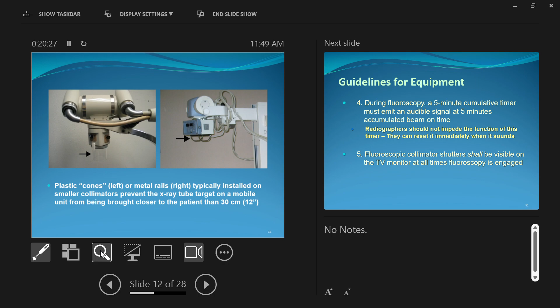In fluoroscopy, which is video x-ray, don't worry too much about this, because you don't do fluoroscopy, right? There has to be a 5-minute cumulative timer. Every time we turn fluoroscopy on, it adds time to the timer. Once 5 minutes hits, we have to have an audible signal that lets everyone in the room know we've hit 5 minutes of fluoroscopy time. It is then the radiographer's job, my job, to turn to the radiologist and say, we're at 5 minutes of fluoro time, by the way, right?